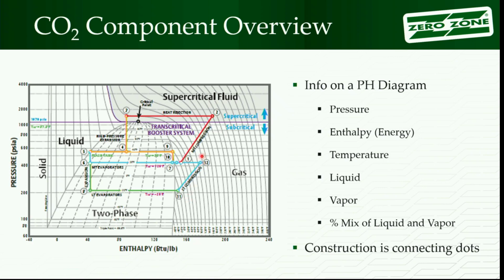Notice our compressors are over here on the right side of the dome because they like gas, right? They don't want to have liquid. In between, it shows you the mixture, and it's an accurate representation of the percent of the liquid in the system and the percent of the vapor. So if you took a chunk of it out and measured it, if you're right down the middle, by weight, half of it would be liquid and half of it would be vapor.